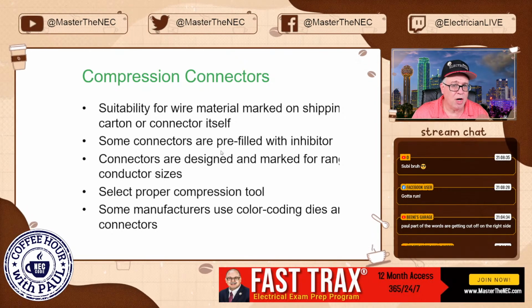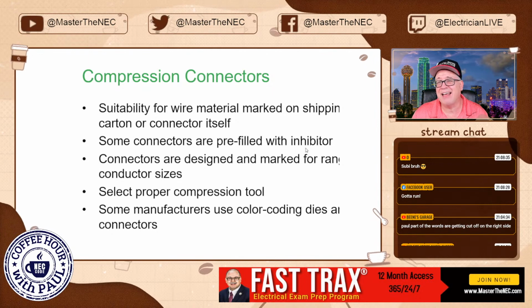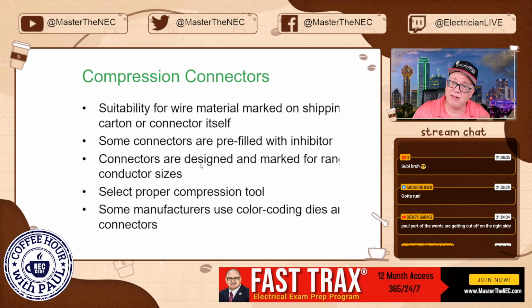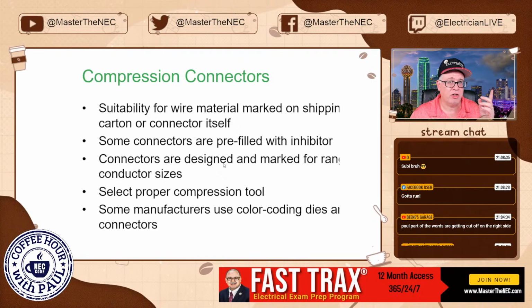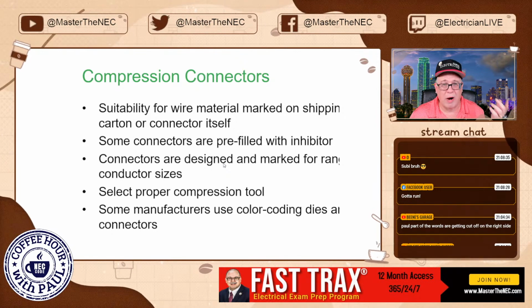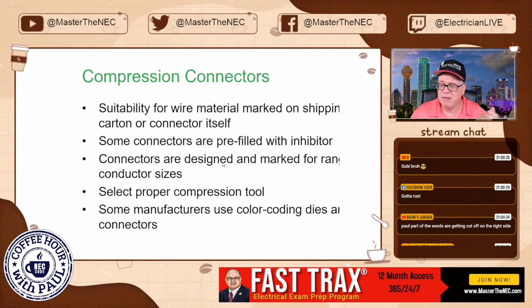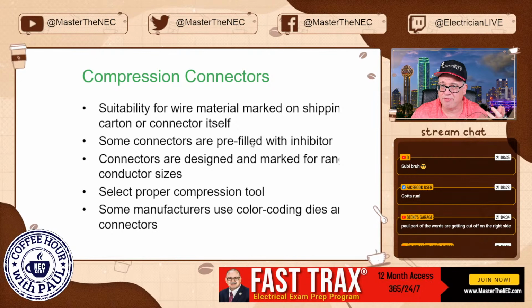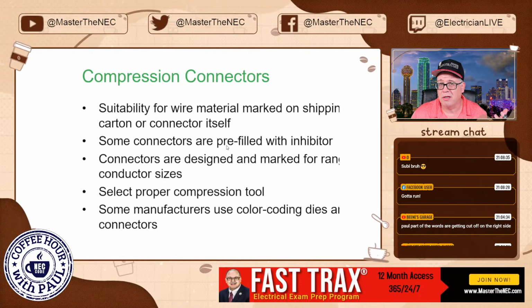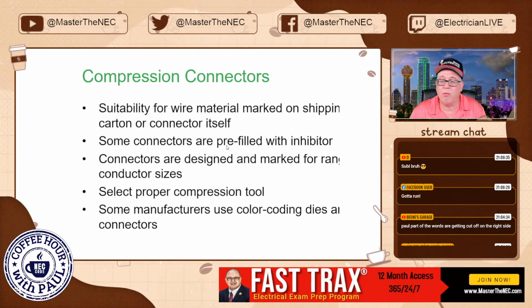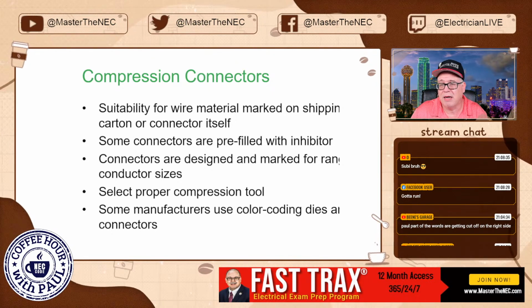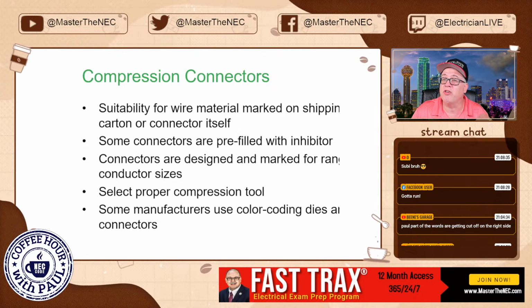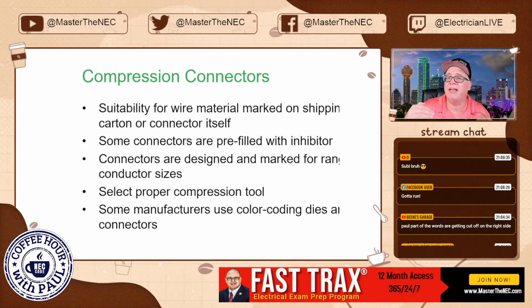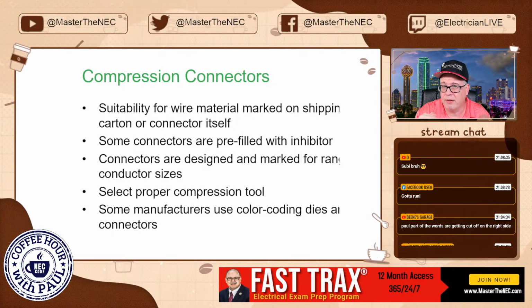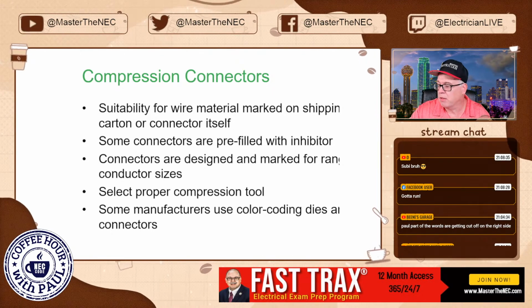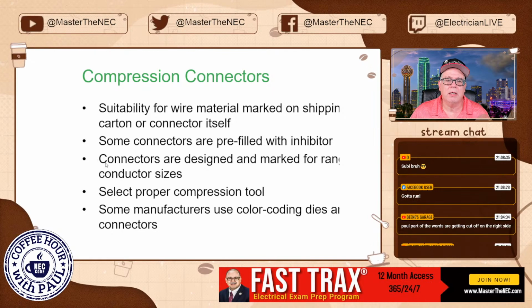Some of them are pre-filled with oxide inhibitor. Some are not. Okay, misconception, aluminum conductors don't necessarily require oxide inhibitor. Okay, but again, if you want to use it, that's perfectly fine. The Aluminum Association recommends it. And we as a manufacturer of wire and cable, we're okay with it. It's not necessarily required, but you might have a situation where a piece of equipment does require it. And if it does, then make sure you follow the rules.